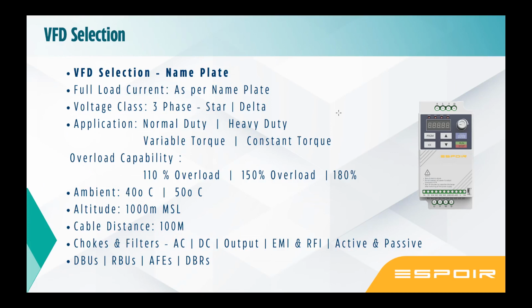Then comes what chokes are available. There are 3 chokes: AC, DC, output. Input choke, DC choke, output choke. All 3 have very different purposes. The AC choke is primarily to protect the input side, and to an extent it reduces the harmonic distortions in the system. Again, it is a very deep subject we need to discuss. The DC choke is primarily to reduce the harmonics, which certain brands supply along with the VFD above a certain rating. Smaller ratings don't come with a DC choke. Larger ratings, by default, a DC choke comes. You need to specify to the vendor whether the DC choke is built in or not. If it is not, you need to have a DC choke externally.